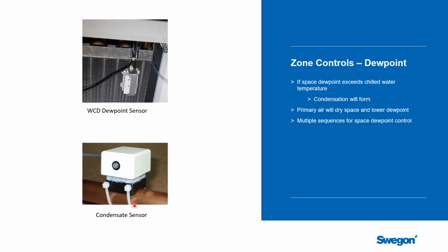But what happens if something goes outside of expectations? An example would be that somebody has the doors propped open to the outside while they're moving furniture in or out, or you have some other event that's adding a lot of humidity to the space. What are we going to do about that? And so you tend to get 2 approaches. What I'm showing up here is some form of dew point sensor. It's actually on the coil inside the chilled beam, so as the air from the room is drawn through the chilled beam, it's actually being pulled across the sensor, so it's a good place to mount the sensor. It's out of sight, nobody would see it. The cover is off right now.